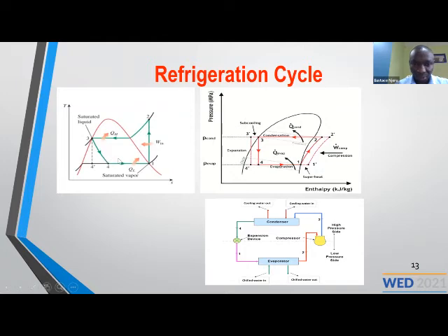So if you are able to reduce the length of this line by offsetting the temperature here, or improving the rate of heat exchange between the fluid being cooled and the refrigerant here, you can operate at a slightly higher temperature, and that will reduce the power input to the compressor.